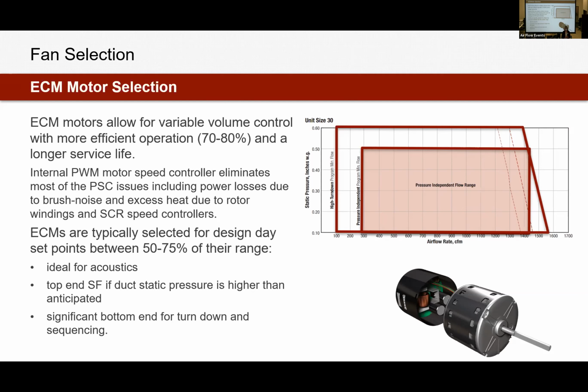Yes, my rule of thumb is always go pressure independent unless there is a scheduled airflow lower than that pressure independent range. So the schedule should note somewhere that they're going to need a big turn down on the fan. If you're dropping below, in this case, that 300 CFM, then I would go high turn down. Otherwise, default to pressure independent.